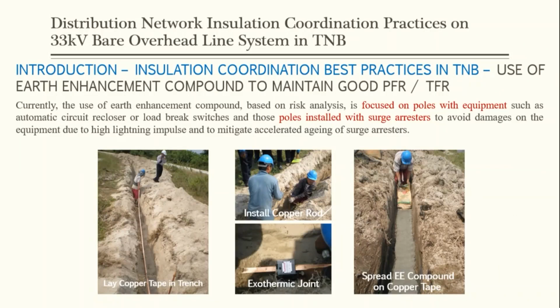Currently, the use of earth enhancement compound based on risk analysis is focused on poles with equipment, such as automatic circuit reclosers or load break switches, and those poles installed with surge arresters, to avoid damage to the equipment due to high lightning impulse and to mitigate accelerated aging of the surge arresters. So we have here from the pictures how we lay the counterpoise copper tape in the trenches. We install the copper rod, and we have to make sure that the counterpoise earth tapes are joined using exothermic joint. And lastly, we spread the earth enhancement compound on the copper tape before we put back the soil on top of it.